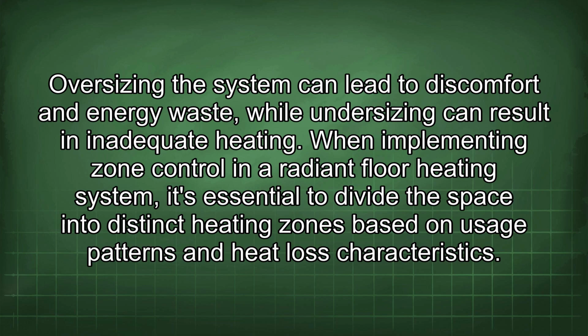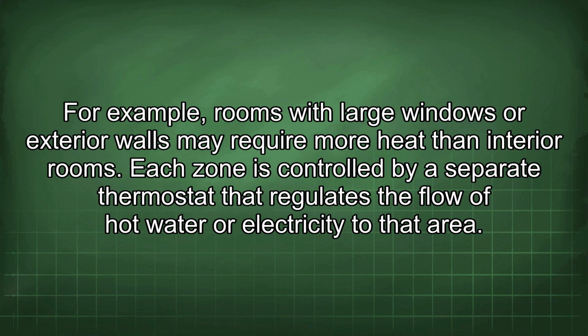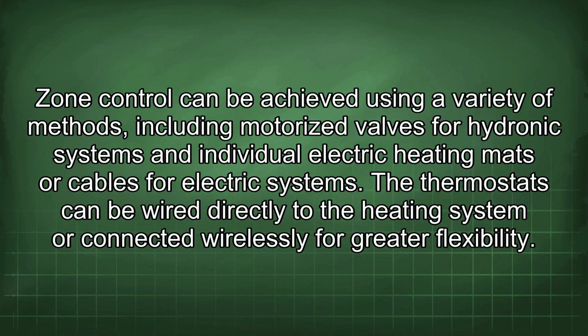When implementing zone control in a radiant floor heating system, it's essential to divide the space into distinct heating zones based on usage patterns and heat loss characteristics. For example, rooms with large windows or exterior walls may require more heat than interior rooms. Each zone is controlled by a separate thermostat that regulates the flow of hot water or electricity to that area. Zone control can be achieved using a variety of methods, including motorized valves for hydronic systems and individual electric heating mats or cables for electric systems.